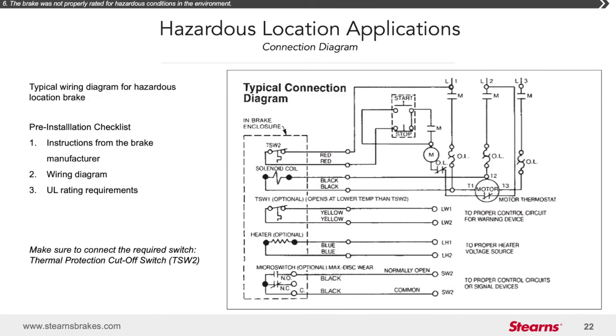So I wanted to give you an example of a typical wiring diagram for a hazardous location brake and give you this pre-installation checklist. It's important to have the installation instructions from the manufacturer. You may get a brake already attached to a motor or already attached to some OEM equipment, but it may not be wired yet. So what you're going to see is a conduit elbow, a sealed conduit elbow with different color wires coming out.